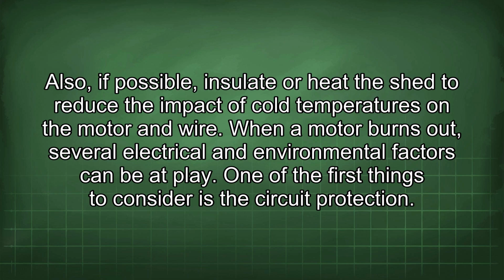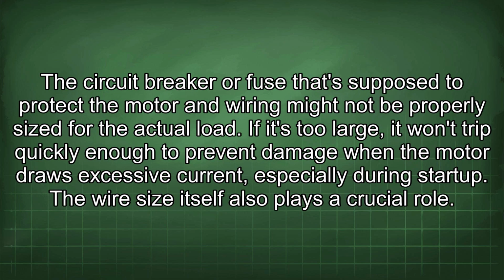When a motor burns out, several electrical and environmental factors can be at play. One of the first things to consider is the circuit protection. The circuit breaker or fuse that's supposed to protect the motor and wiring might not be properly sized for the actual load. If it's too large, it won't trip quickly enough to prevent damage when the motor draws excessive current, especially during startup. The wire size itself also plays a crucial role.